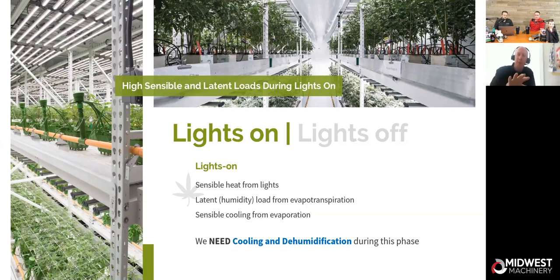So when we're in the lights on, we're going to need cooling, just temperature change, and we're going to be needing dehumidification. Now at the beginning, cooling will be highest when the plants are small, but then as the plants grow, the sensible cooling need will drop. And as the plants grow and they drink more water, the latent moisture removal goes up.